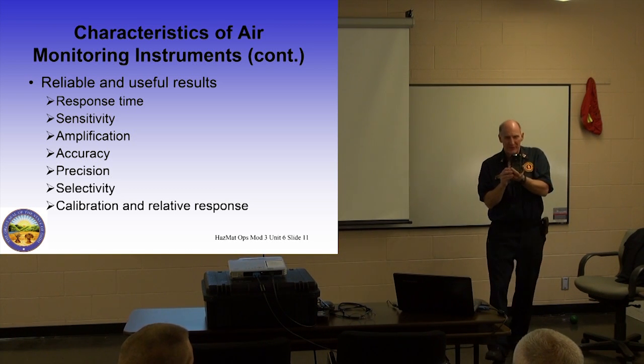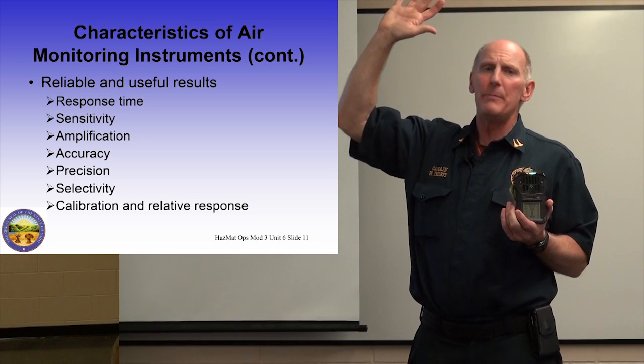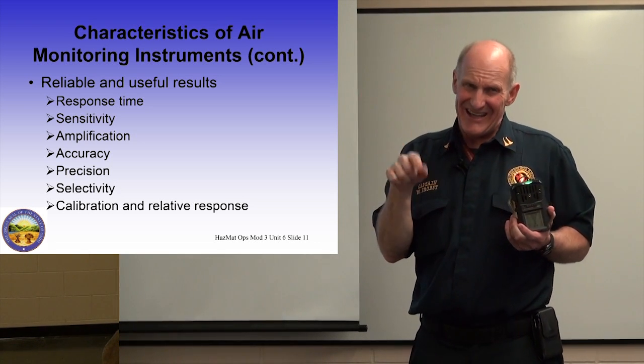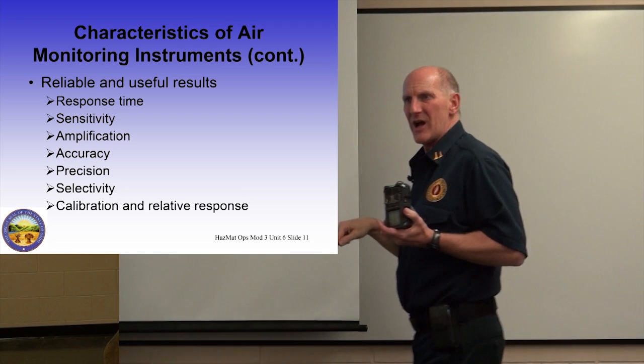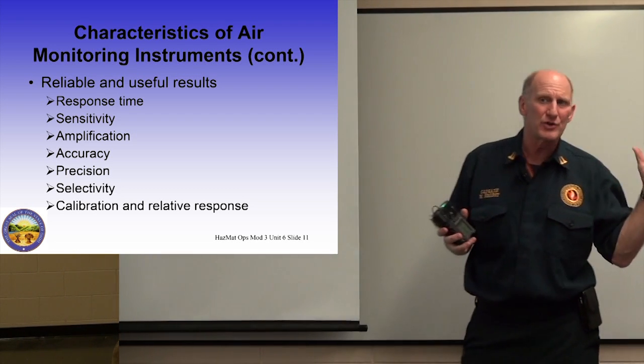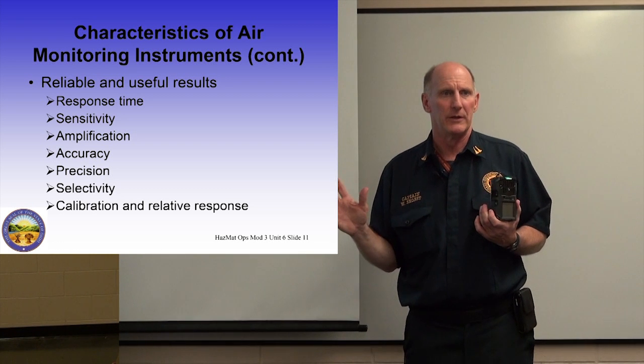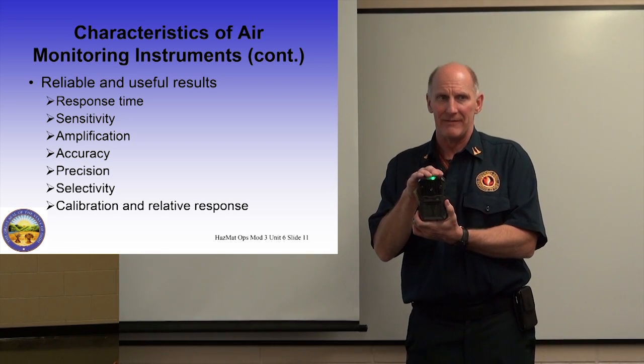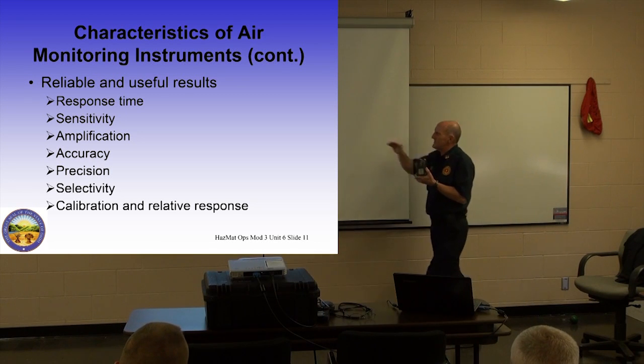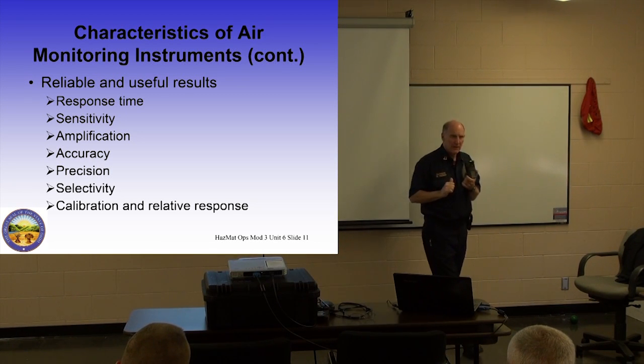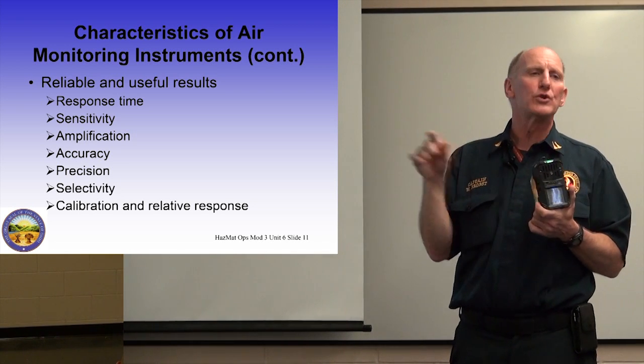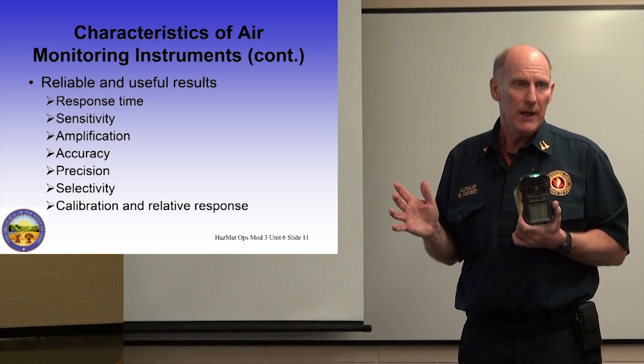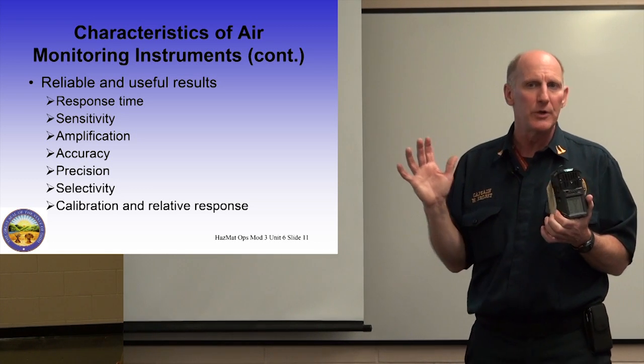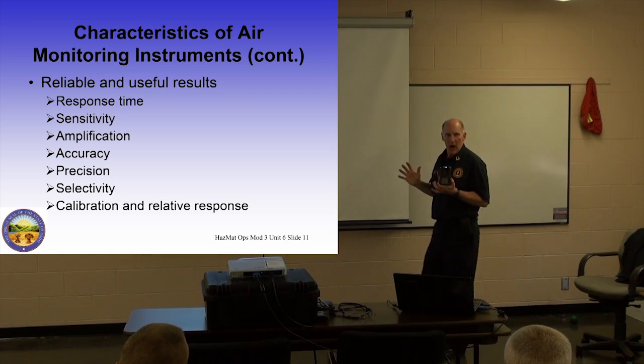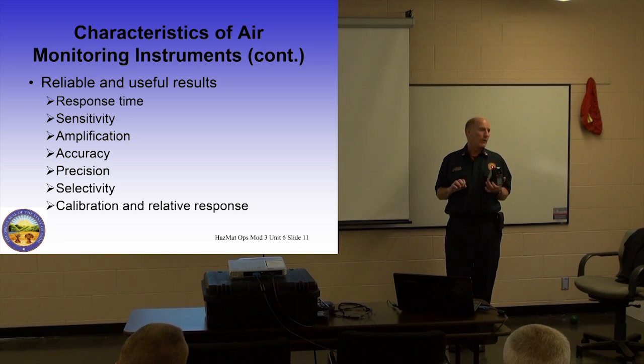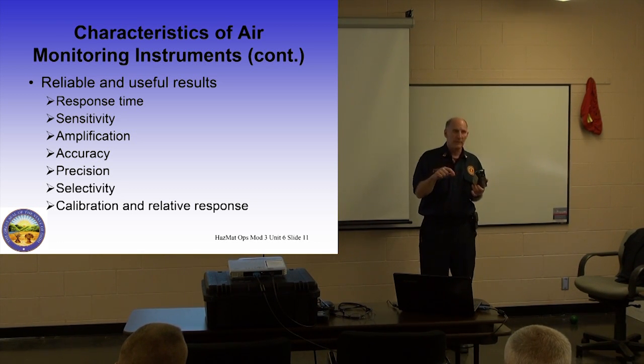Accuracy. How accurate is it? Meaning, if it's measuring 3 parts per million of carbon monoxide, is it really 3 parts per million of carbon monoxide, or could it be as many as 10 parts per million or as little as 2 parts per million? And so I want to know the accuracy of it. Again, the problem with these instruments is they are not accurate. They all will tell you there's a certain percentage point to their accuracy. And so I never want to look at 3 parts per million as being exactly 3 parts per million. I just want to know it's somewhere, and I want to know that a reading of 3 is a little bit less than a reading of 5.